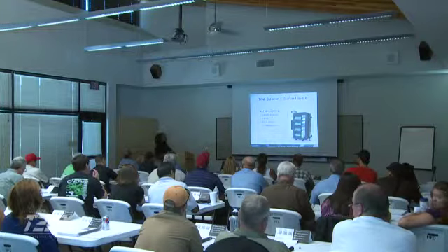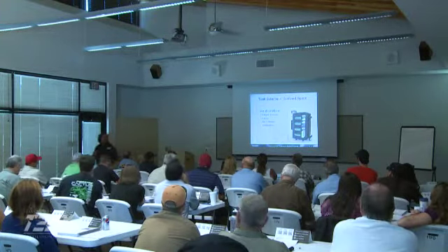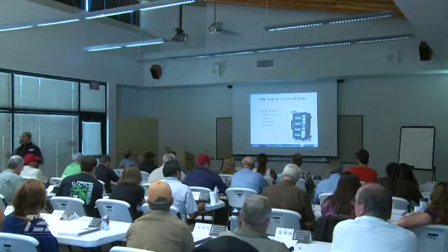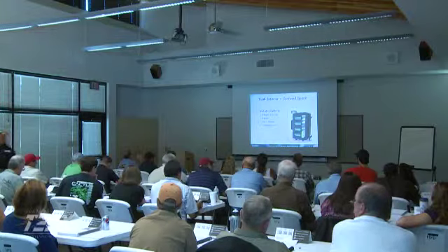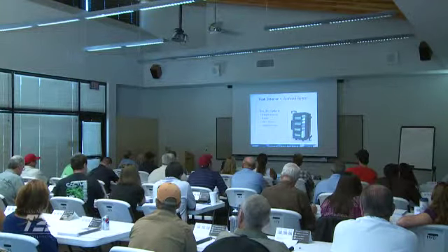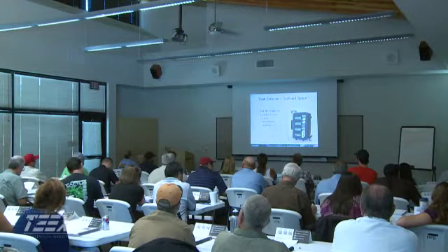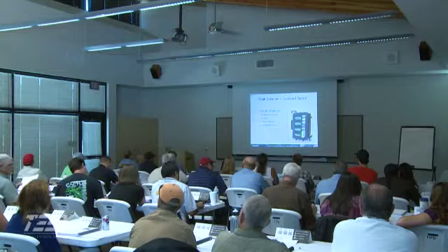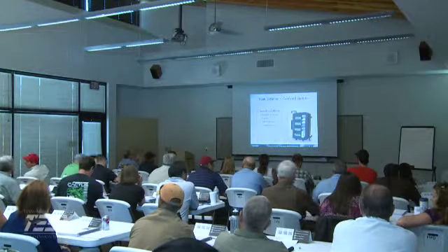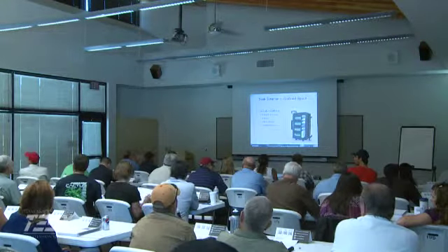We want to test the atmosphere for gases. You're going to test for oxygen first, because the number one cause of death in a confined space is the lack of oxygen. If there's no oxygen in there, I need to put on some additional oxygen, right? So test for oxygen first. Then I'm going to test for what? Which gas? Combustible gases. I heard methane, very good.